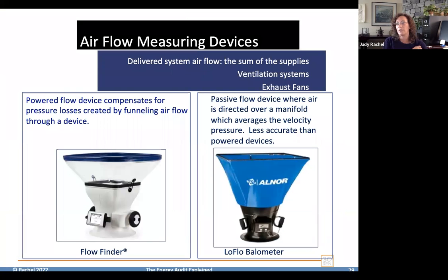And here are some other airflow measuring devices. These devices are great for our exhaust fans and our supply grills and registers, to tell us whether those exhaust fans are actually moving the amount of air that they should to exhaust pollutants, and whether the supply registers or grills are actually delivering the amount of air that they should, that the overall system should. The flow finder on the left is the most accurate device, and it's a powered flow hood. The Alnor low flow balometer on the right has definite accuracy problems because it's not a powered flow hood.